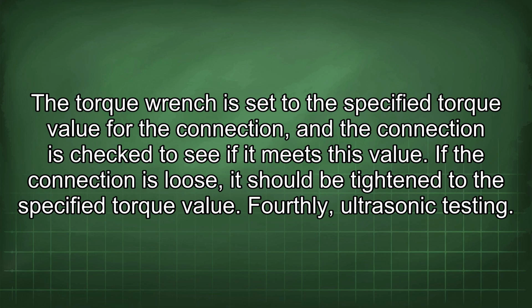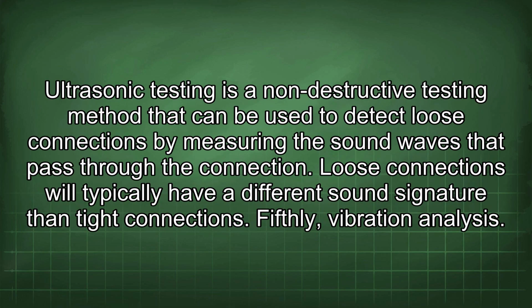If the connection is loose, it should be tightened to the specified torque value. Fourthly, ultrasonic testing. Ultrasonic testing is a non-destructive testing method that can be used to detect loose connections by measuring the sound waves that pass through the connection. Loose connections will typically have a different sound signature than tight connections.